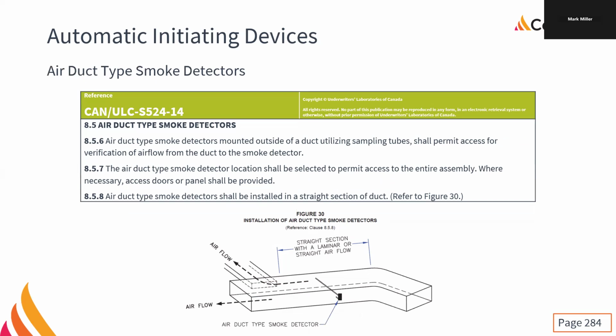So we need clean airflow. We put them in a straight section of duct, and we have to be downstream of all bends, right? Ideally, we want to be 6 duct widths downstream, but we also want to be at least 1 duct width upstream of any corner or T or anything like that, because that corner is going to cause disturbances in the airflow, and it could be enough that it disrupts the airflow where we have the smoke detector. So we want to be a little bit upstream as well. So it can be frustrating trying to find good locations, and then you have to argue with the general contractor. It's like, yeah, the duct smoke has to go right here. You need to put in a hatch, and they don't want to put in hatches and all that stuff.